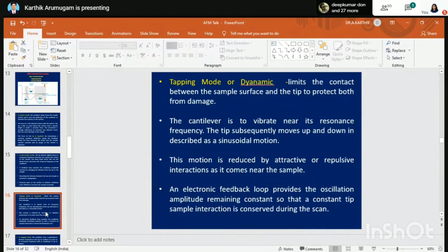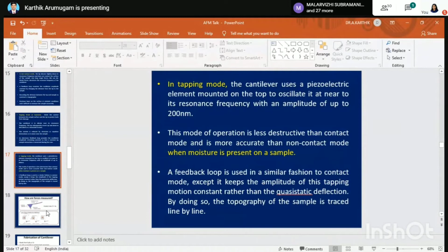Here is one important point we have to discuss: the mode of operation. This tapping mode is less destructive than the contact mode because the tip does not touch the surface of the sample, and it is more accurate than the non-contact mode, right? Anyway, the feedback loop is very, very important. Every time I say that the feedback is very important, it is because the feedback loop controls the particular height of the tip, right? What is the actual distance we are keeping? Depending upon the actual distance, we may classify it as the tapping mode, the non-contact mode, or the contact mode, right?